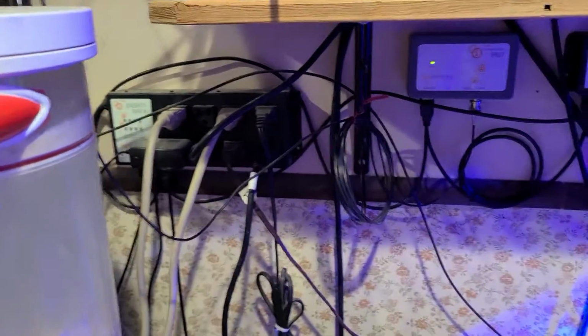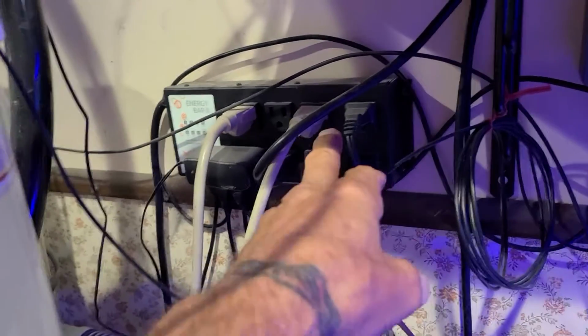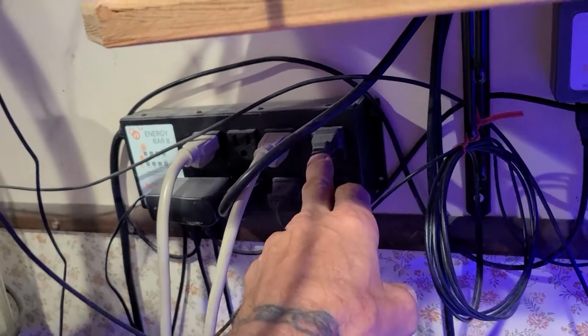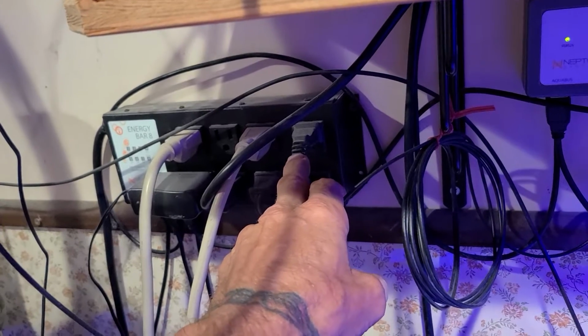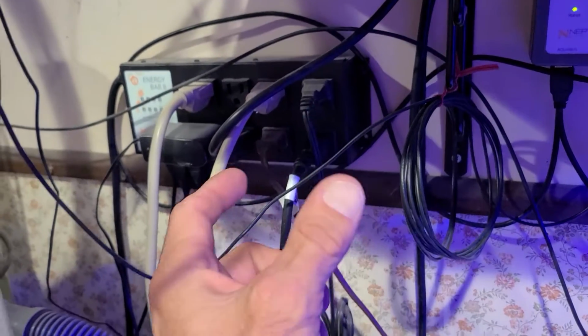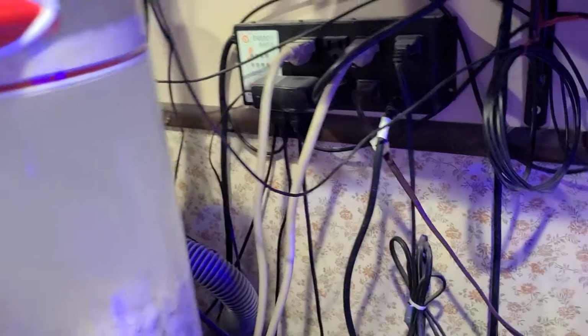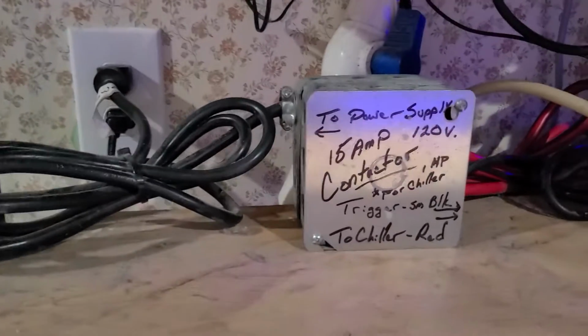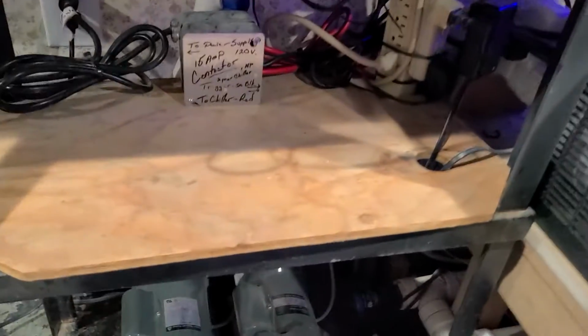So to prevent that, what I do is I use an outlet as a trigger source. It's kind of low amperage, and basically it pulls the coil in on the contactor, and I shall show you that. I'm going to put you on pause while I pull it open. I have my system here disassembled a little bit so you can see what's going on.